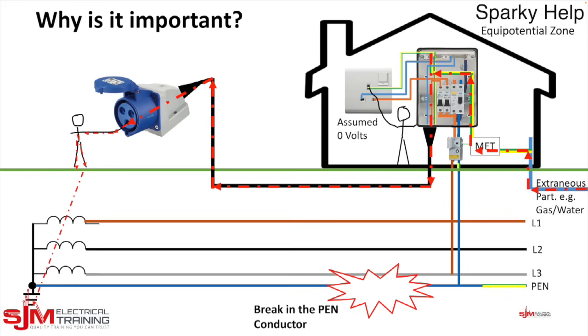So now current from somewhere else, or from within the building itself because you've lost the PEN, so anything that's turned on within the building, could now flow through the CPC to the socket outdoors or the supply outdoors, which someone could be touching, and because they're close to the transformer, they could form that path. So that again could be potentially dangerous for that person. These are quite serious things to happen.